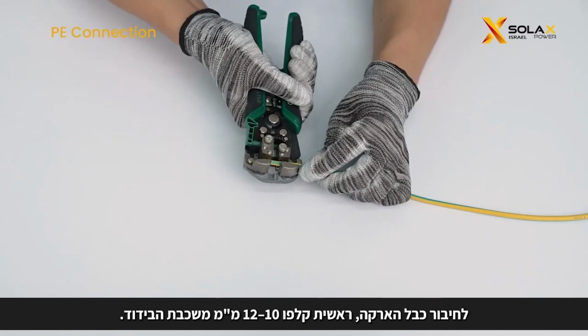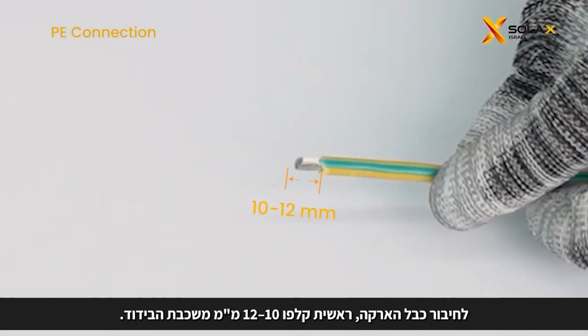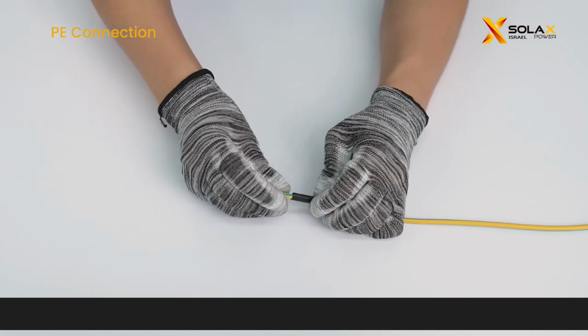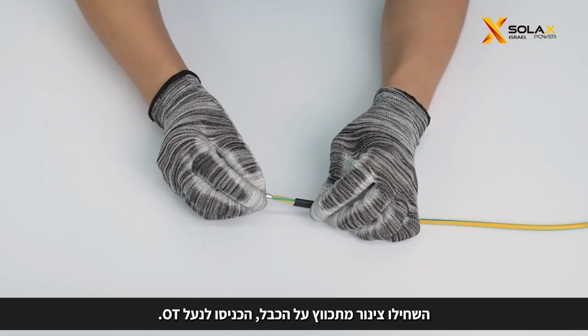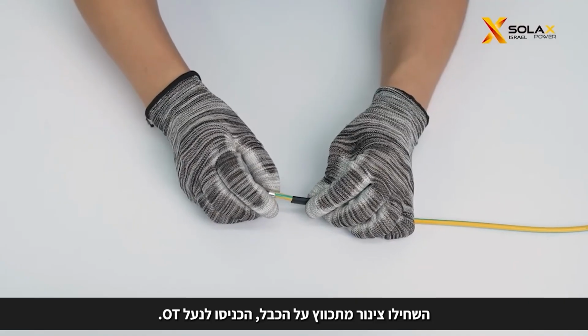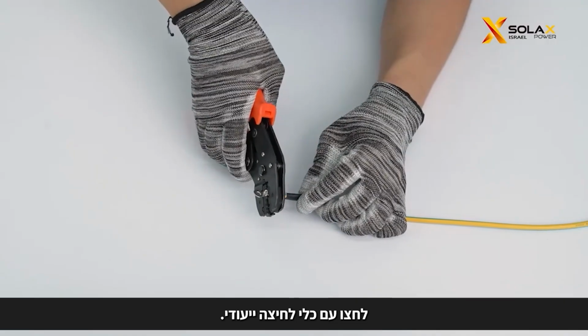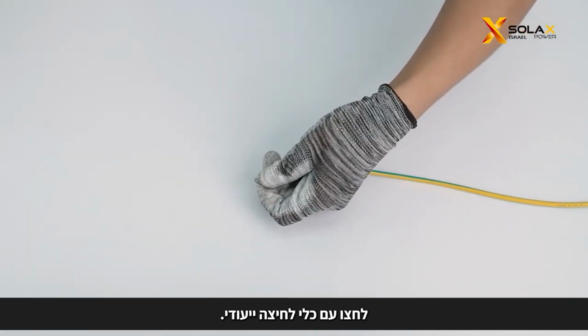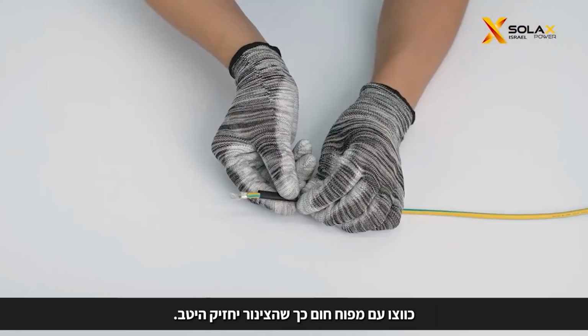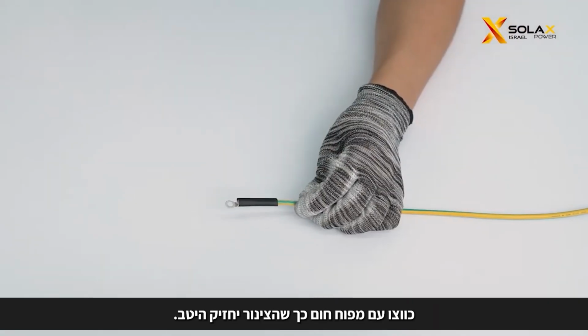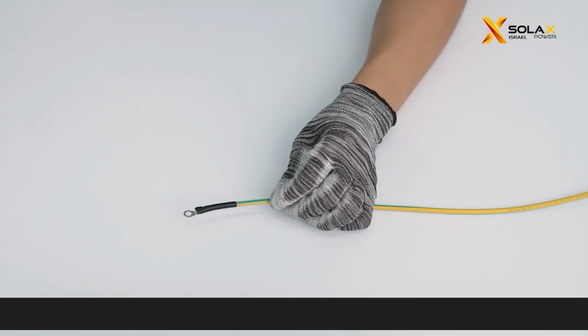For ground cable connection, firstly, strip 10 to 12 mm of the grounding cable insulation. Put on heat shrink tubing. Insert the stripped cable into the OT terminal. Crimp the OT terminal with a crimping tool. Then use a heat gun to shrink the tube so that it can be firmly contacted by the terminal.